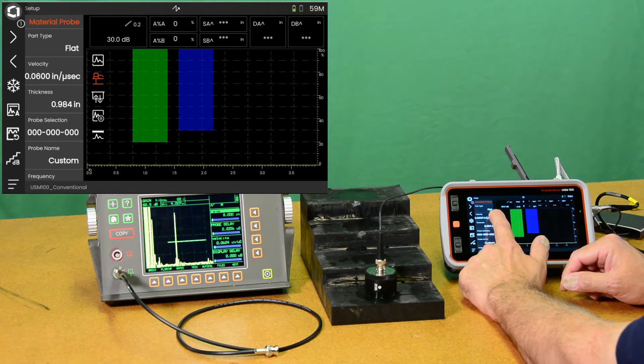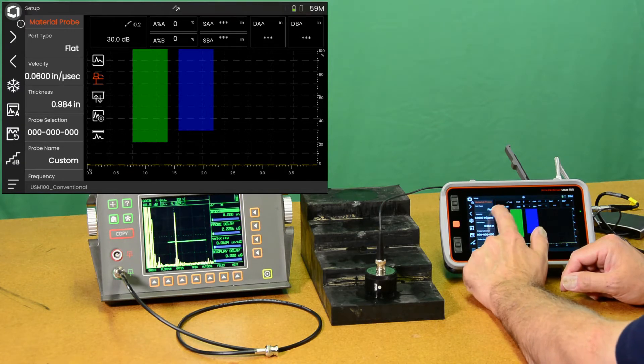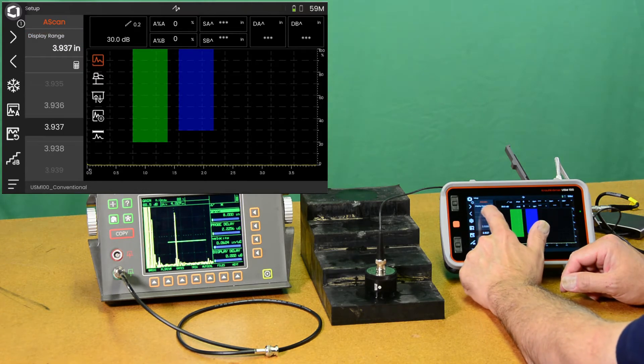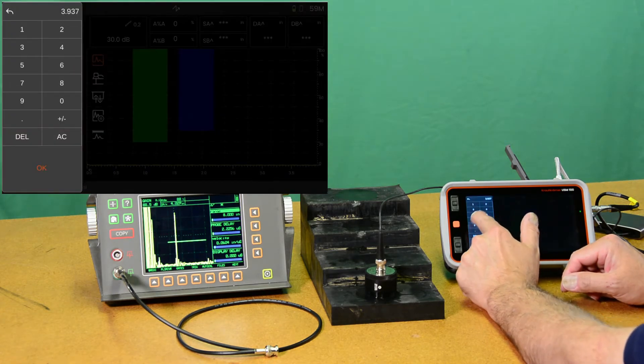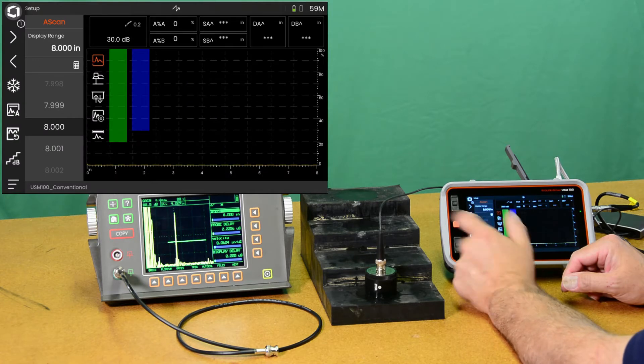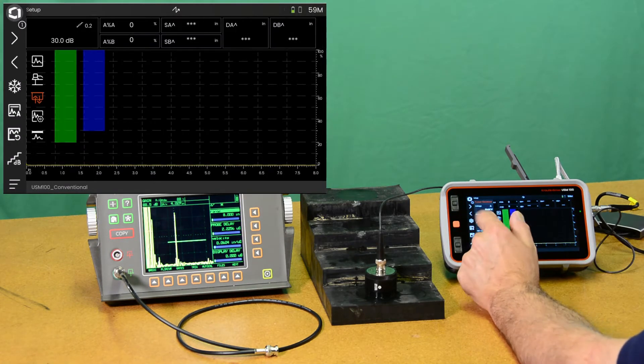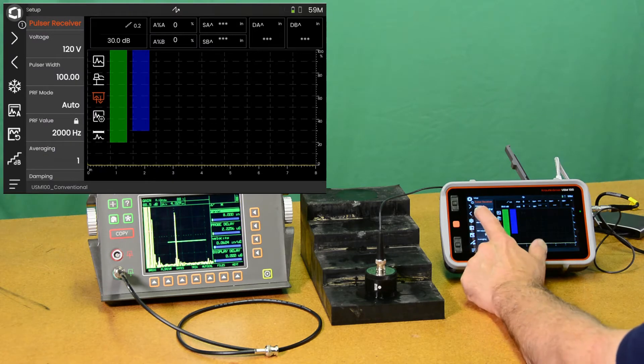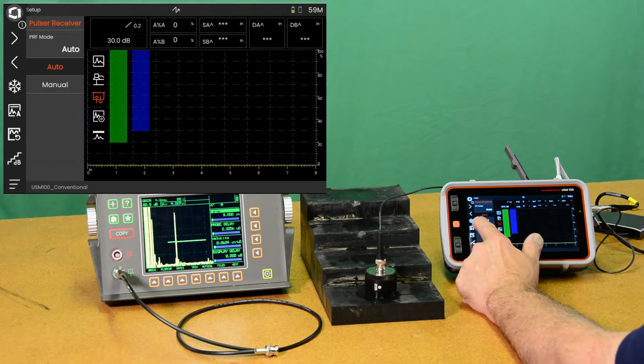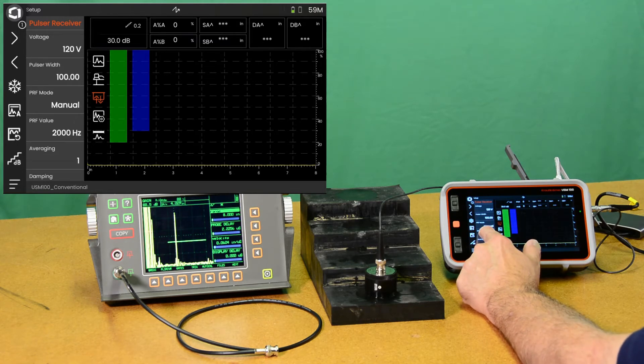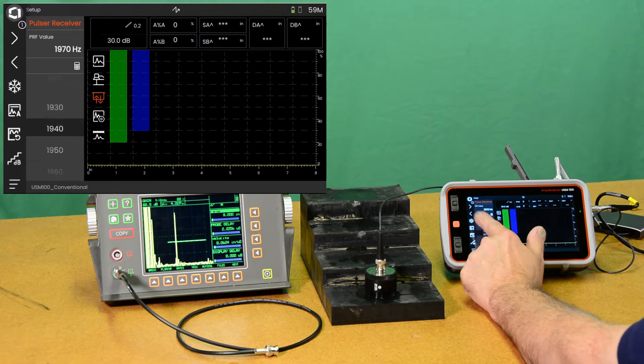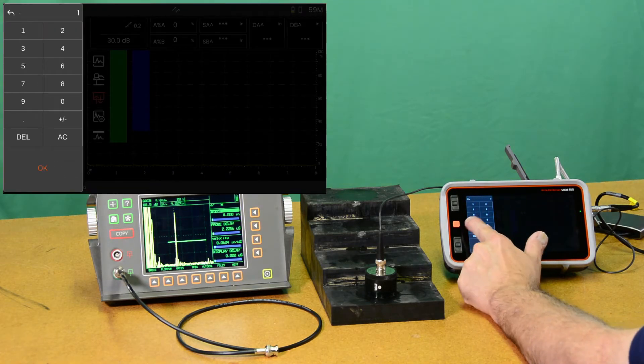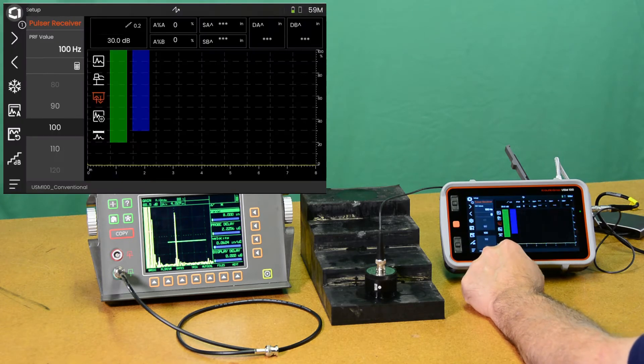And we're going to go to our A-scan menu and tell it that we want 8 inches of display range. That would be nice for looking at the various steps in the block. And we'll go to the Pulser Receiver menu. The first thing we're going to do is go to manual PRF mode. We want to set our rep rate low because we're using a very wide pulser. We're just going to go right to 100 hertz.